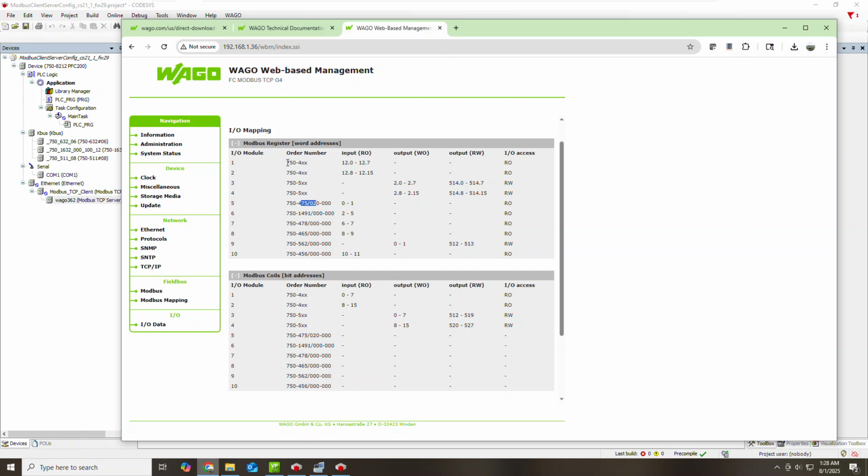And then, of course, if you want to read it as a register, you see that the first digital input starts at register 12. That's because on the coupler, analogs get mapped first. So here's the first analog from left to right, address first, and then 0 and 1.